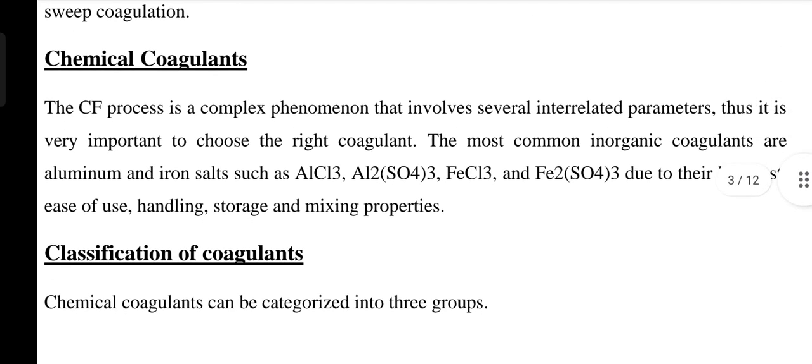What are chemical coagulants? The coagulation flocculation process is a complex phenomenon involving several interrelated parameters, so it is very important to choose the right coagulant. The most common inorganic coagulants are aluminum and iron salts, such as aluminum chloride, aluminum sulfate, iron chloride, and iron sulfate, due to their low cost, ease of use, handling, storage, and mixing properties.